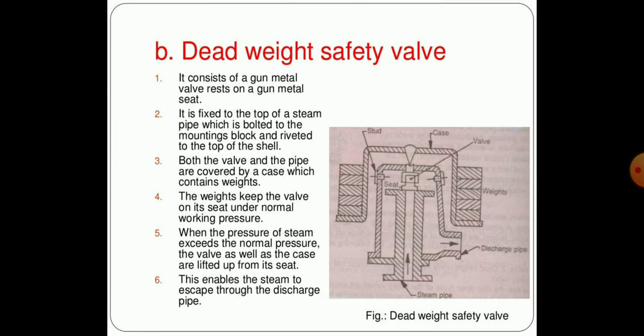Both the valve and the pipe are covered by a casing which contains the weights. The weights keep the valve on the seat under normal working pressure. When the pressure of steam exceeds the normal pressure, the valve as well as the casing is lifted up from the seat, which enables the steam to escape through the discharge pipe. As soon as the pressure falls back, the weights exert pressure and the valve retains its original position on the seat, which blocks the steam from escaping the container.